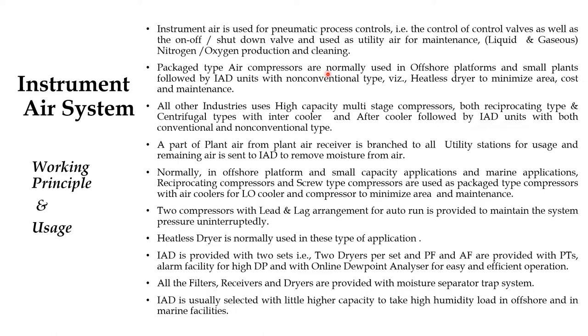Usually package air compressors are normally used in offshore platforms and small plants, followed by IAD units with non-conventional type — that is heatless dryer — to minimize area, cost and maintenance. It is also used in marine systems. All other industries use high-capacity multi-stage compressors, either reciprocating type or centrifugal types, with intercooler and aftercooler followed by IAD units with both conventional and non-conventional type dryers.